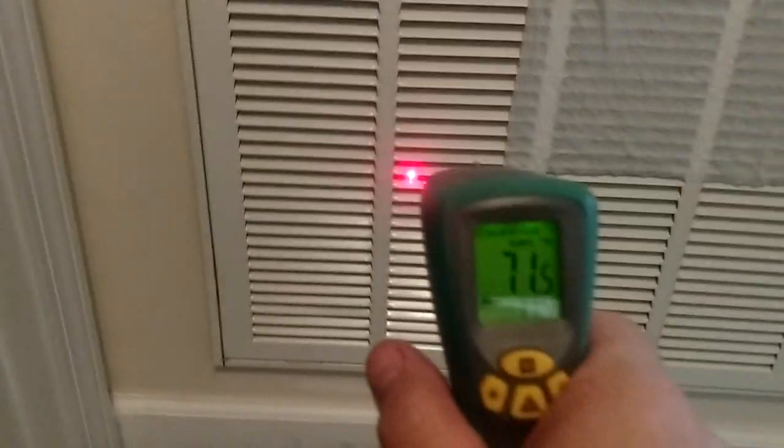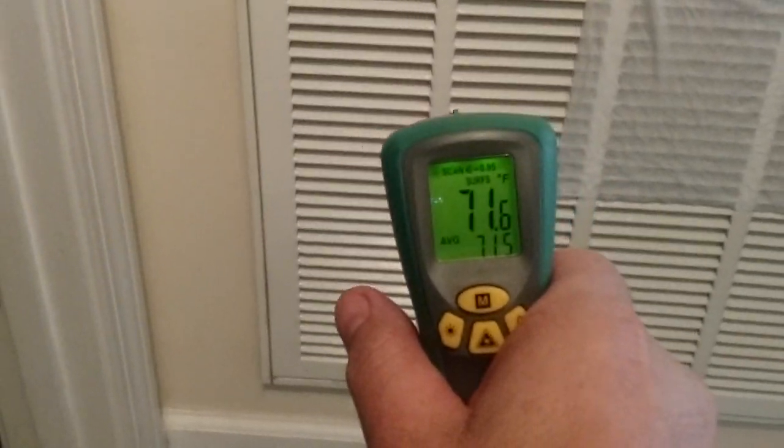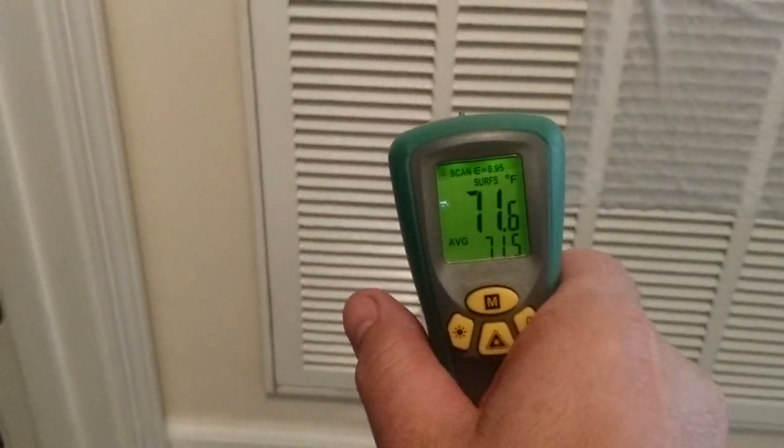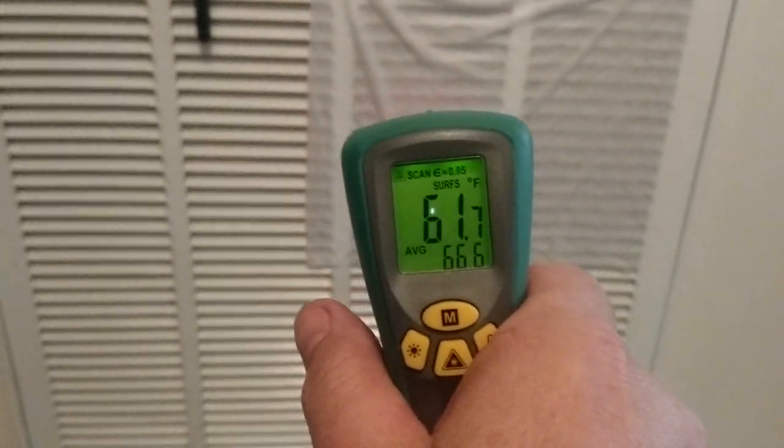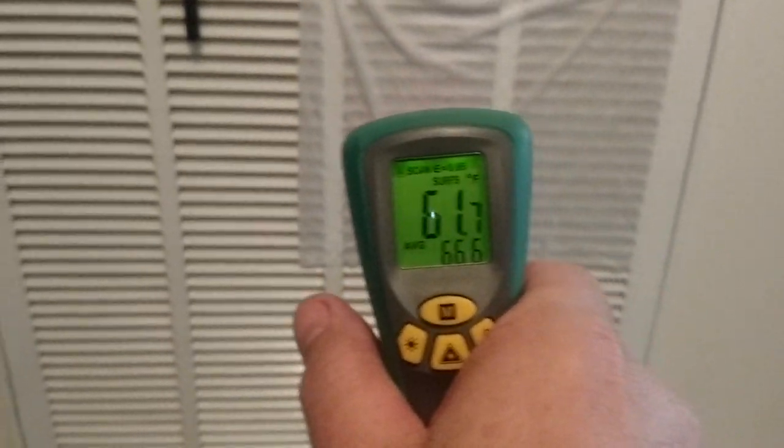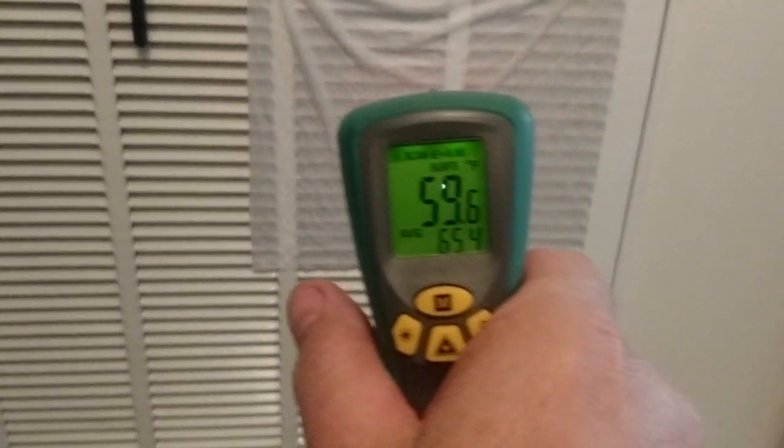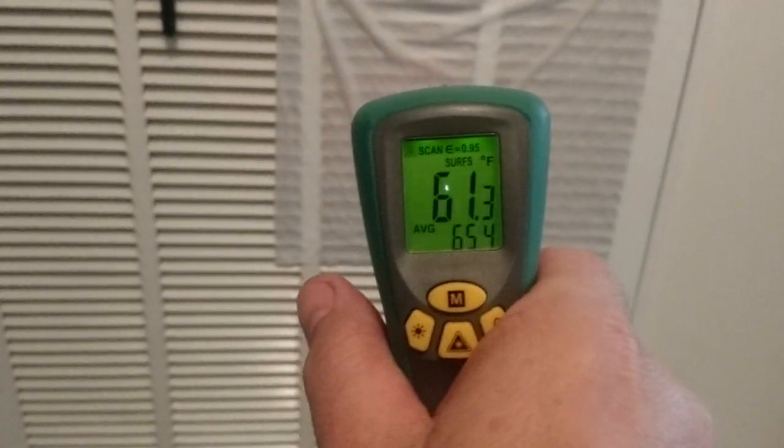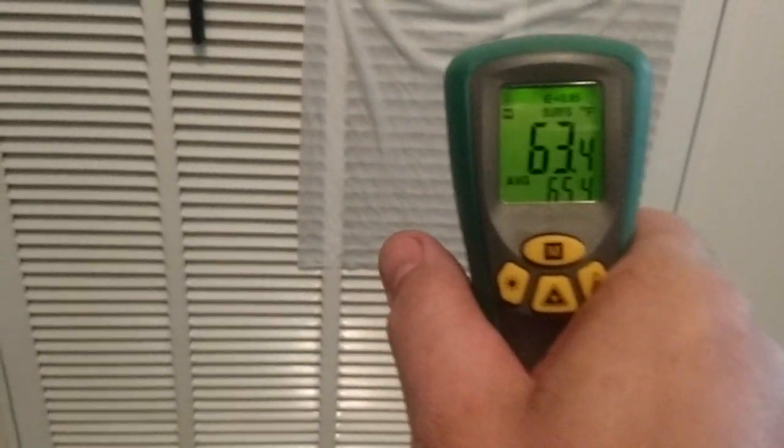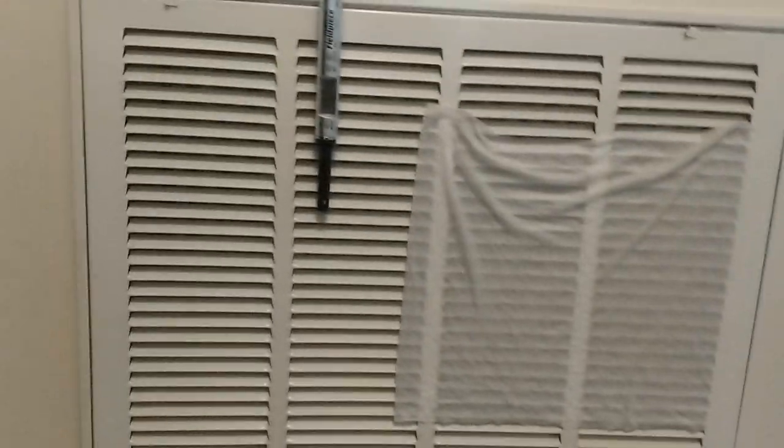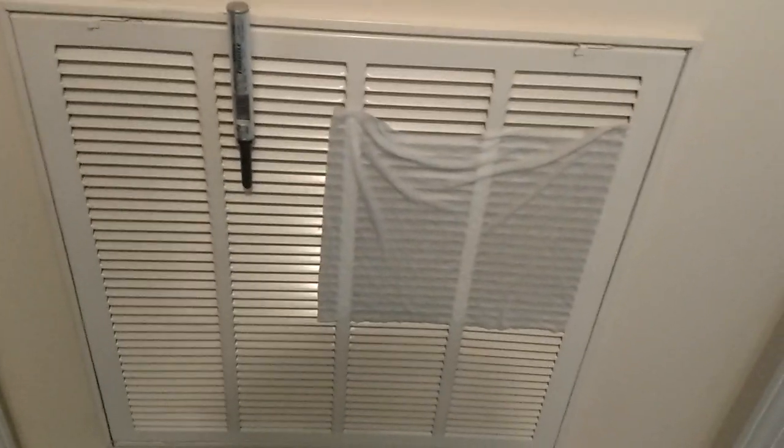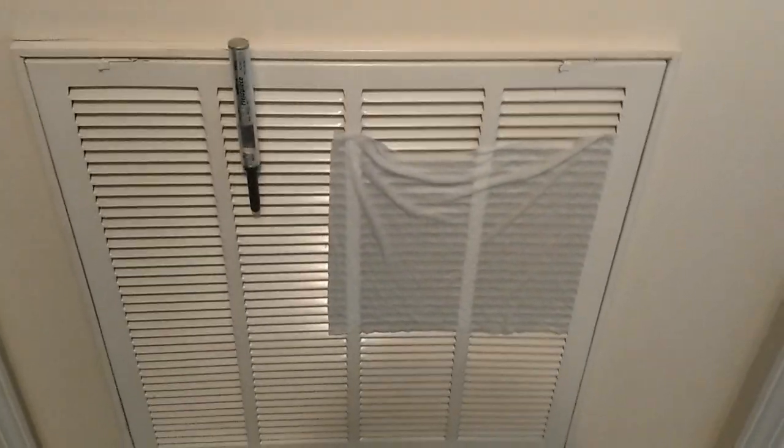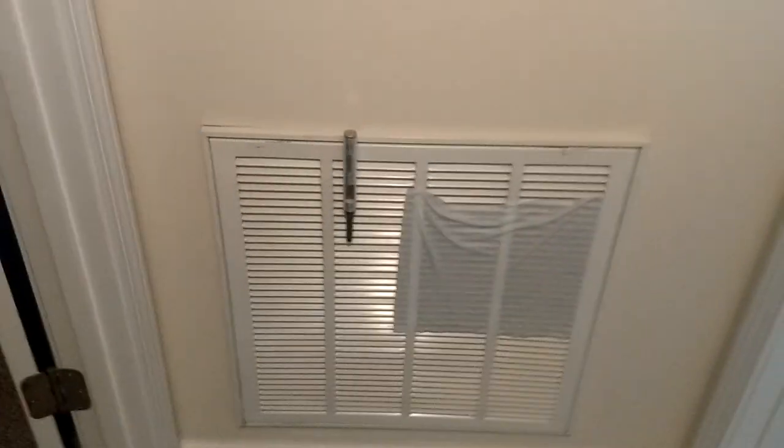Right in that range. If you shoot it over here you can see the dry bulb is 71, but then you see the difference there. We're right there at 61, 62, depending on where you hit it - 59, kind of jumping around. That is right in the ballpark, plenty close enough to get the superheat within that five degree range. In a pinch that does work - I've tested it numerous different times.